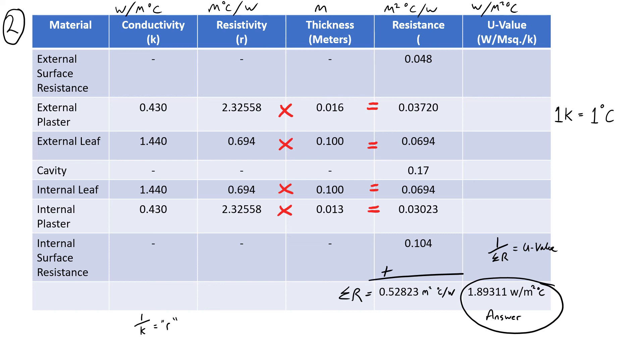Once the resistivity column is filled, multiply resistivity by thickness to get the resistance for each layer. Once all resistances are calculated, find sigma R — the total of all R values — with units of metres squared degrees Celsius per watt. Finally, divide 1 by the total resistance to get the U-value of the wall. That is the complete method.